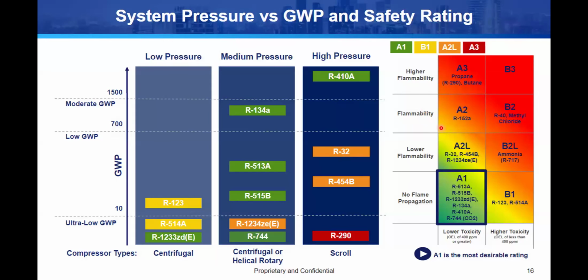So there's a bunch of ones, specifically 6 for HVAC, that are on the very bottom of this flammable bucket. They're just right on the line here. And what the ASHRAE folks did, I assume, is that they wanted to put them down in the A1, but you can't change something after it's classified decades ago, right? Nothing changed about the property of the chemicals. So what are you going to do? I think what they did is they just created another bucket. They're just like, what if we make another bucket and we take all the stuff that's barely an A2 and we call it A2 light, like just a little bit flammable? And that's how we get A2L. It's the refrigerants that are flammable, but just barely flammable, not even as flammable as a regular A2.